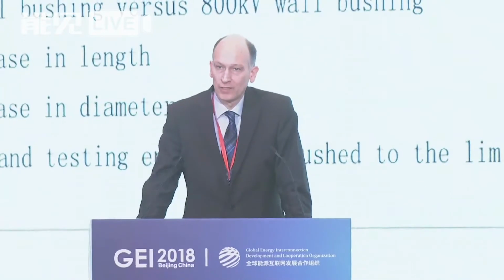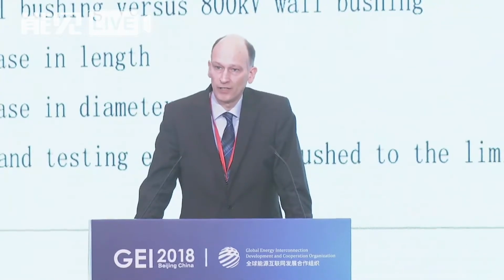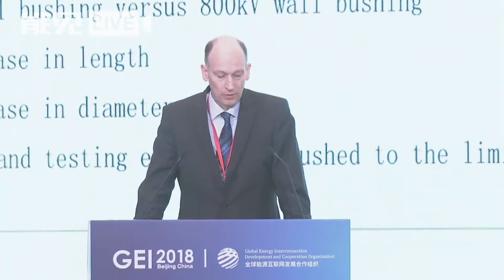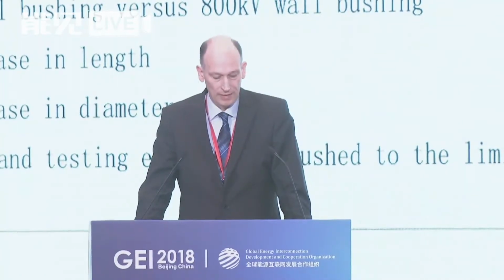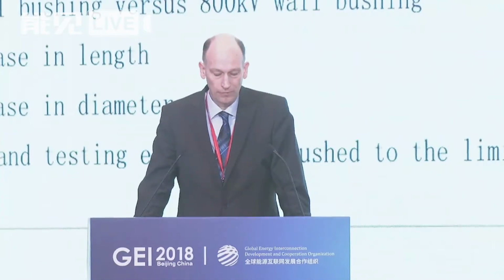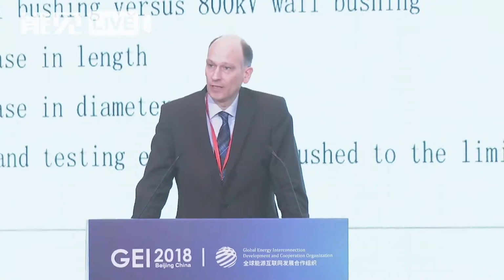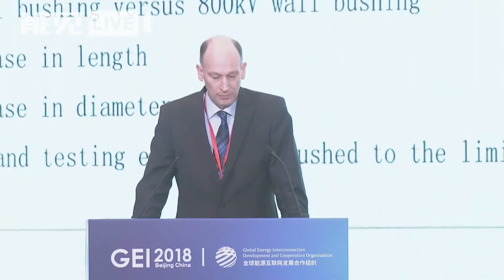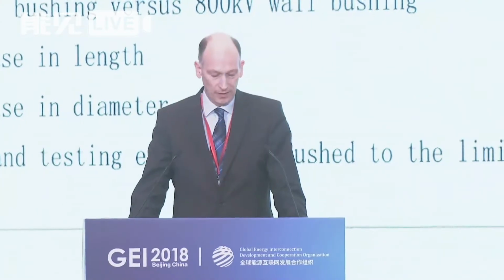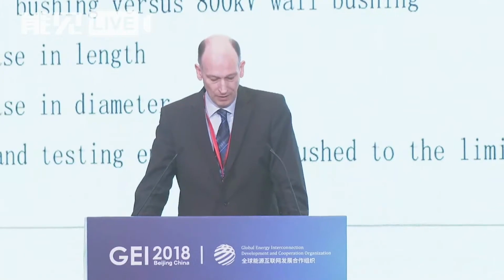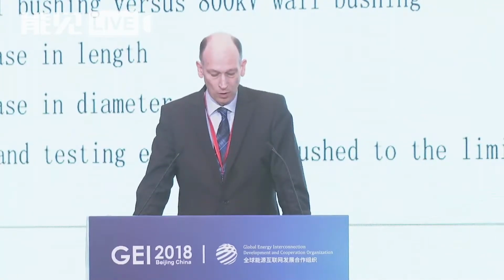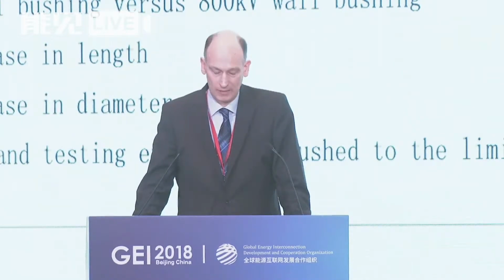The bushings are a substantial and challenging part of the transformer - we're talking wall bushings as well as transformer bushings. The biggest challenge was to transfer 50% more energy at an even increased voltage level, so new concepts of insulation were needed in terms of thermal management as well as mechanical design. Comparing the 1100 kV wall bushing to the 800 kV wall bushing, there was a 40% increase in length, a 30% increase in diameter, and the production and testing environment was pushed to its limits.